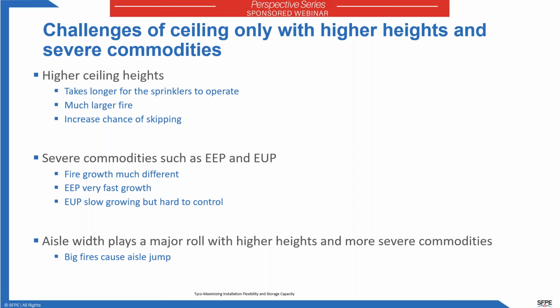Commodities can have a big impact on fire growth. Exposed expanded plastics and exposed unexpanded plastics are very different commodities relative to, say, cartoned unexpanded plastics. Exposed expanded plastics has very fast fire growth. Those fires run away quickly. Exposed unexpanded are slow growing, but boy, once they finally do get growing, they're really hard to put out with that heat that's generated.